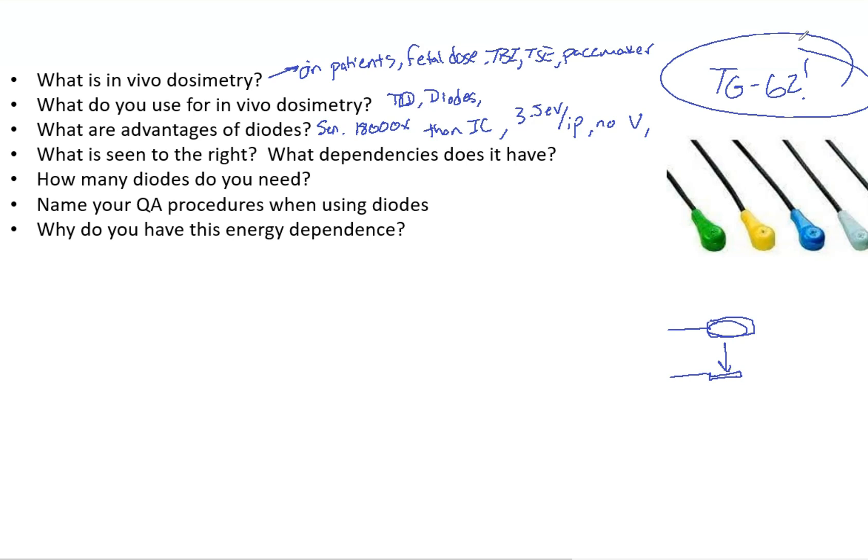So the energy dependence is a big deal with diodes, and that will determine how many we need. So because of that energy dependence, you need a low energy for photons. So that could be 6 to 10 MV. Then you need a separate diode for a high energy photon. So that's going to be 15 to 18 MV. And then you can just have one electron. And so that would give you three diodes for your clinic.